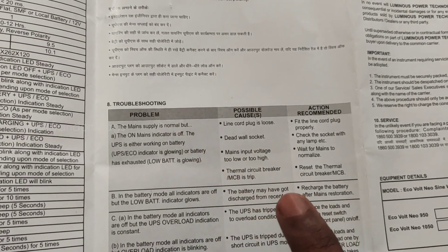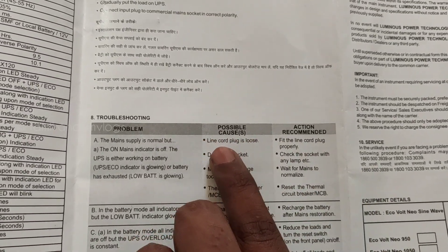But the battery is on backup. The battery is exhausted — low battery indicator is glowing. For possible causes: the line cord plug is loose, the main plug is loose, or the wall socket is faulty.